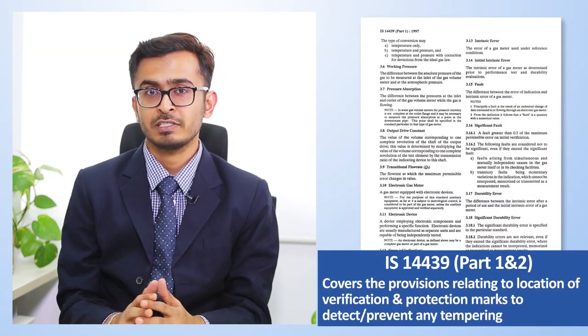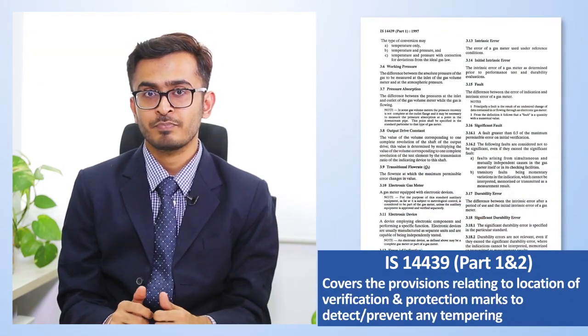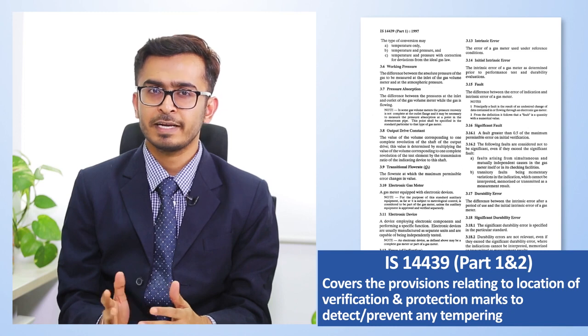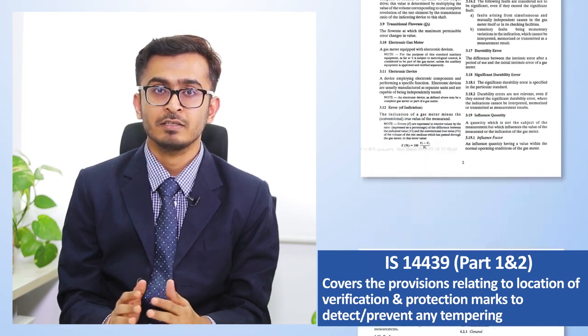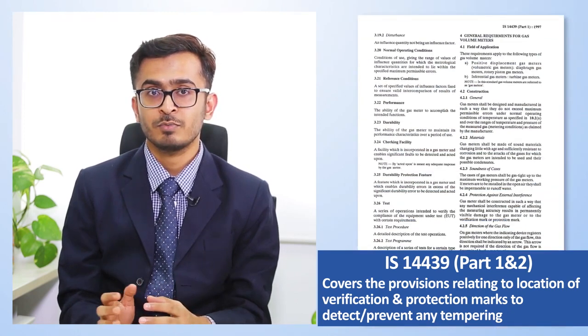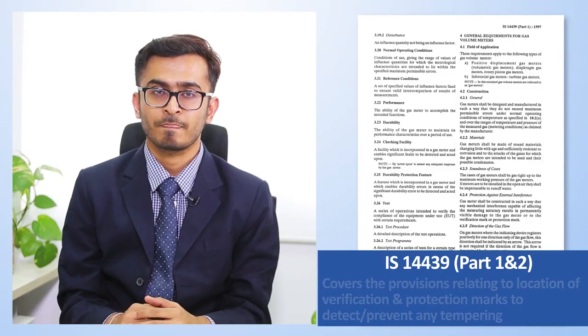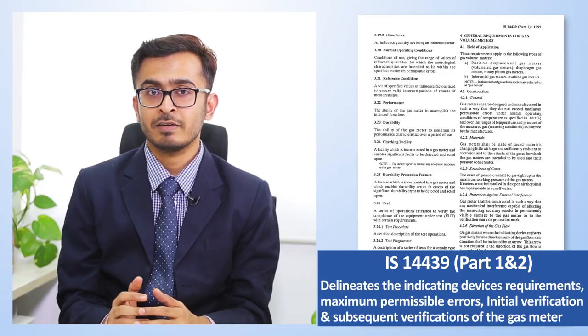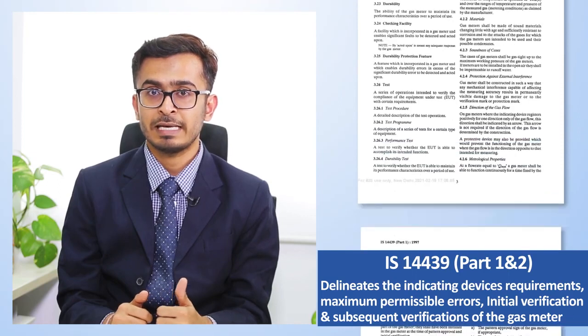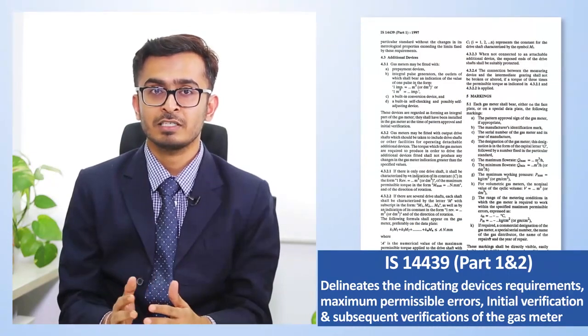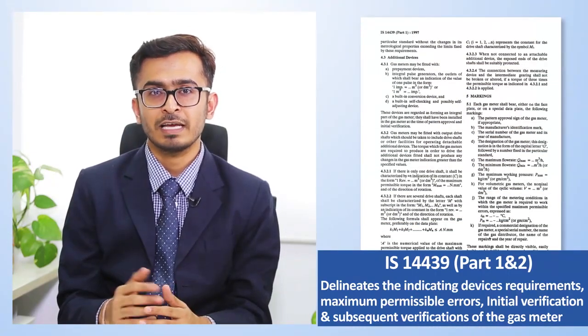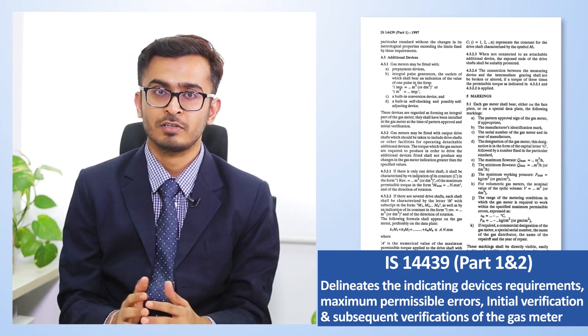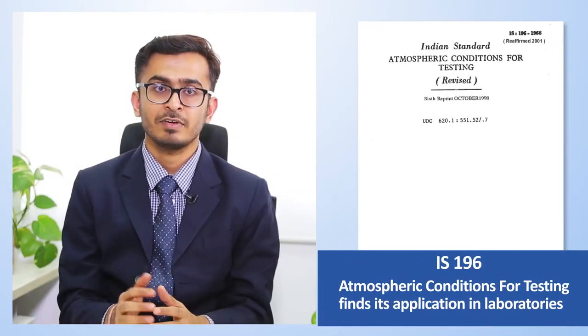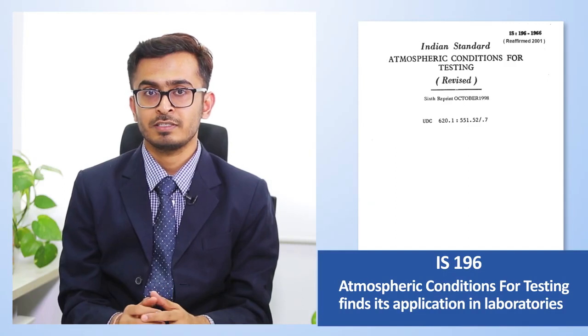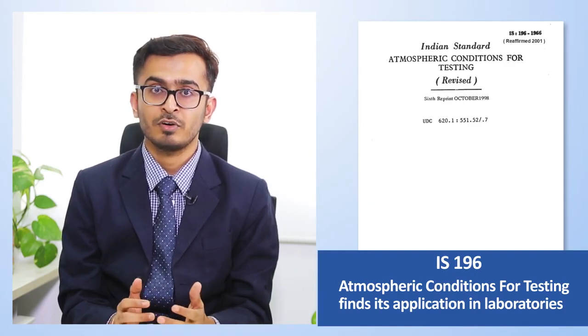It also covers the provisions relating to the location of verification and protection marks to detect or prevent any tampering, and the provisions relating to the pattern approval for metrological control. It also delineates the indicating device requirements, maximum permissible errors, and the initial verification and subsequent verifications of the gas meter by the competent regulatory authorities. Another standard, IS 196, Atmospheric Conditions for Testing, finds its application in laboratories.